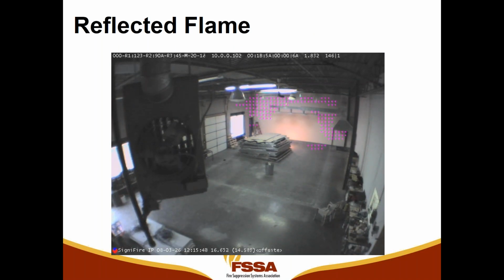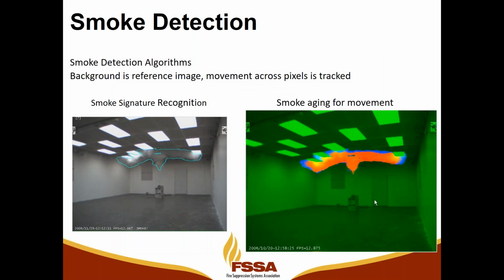Now, this is an example of a reflected flame algorithm. So if you had a radiant energy detector in this space, the energy would be blocked by the stack of material from reaching the radiant energy detector. Video analytics can supplement radiant energy detection or be used on its own to detect the reflection of flame off of reflective surfaces. So in this case, the purple dots represent the reflected flame algorithm. It's very good in spaces where there's a lot of obstructions, mechanical equipment rooms, for example.